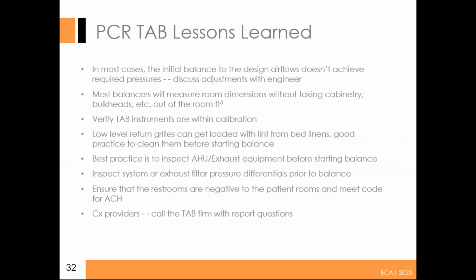Oh, gotcha. So when you're zeroing it out, I guess it doesn't really matter what you're doing with all the other doors. I would say the best way to do it would be to find the transducer that's associated with that pressure monitor, go to the transducer and pull the tubes off of the high and low port. So then the high and low port, no matter what the other doors are doing, are right next to each other.